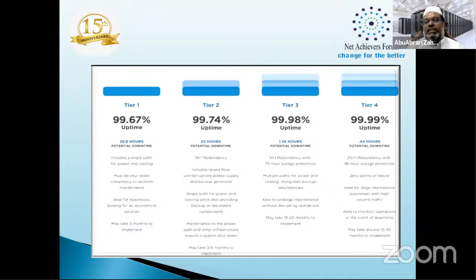Then coming to tier 4, it has 2 N+1, meaning you have one full path for power. For example, it has its own generator, its own UPS, its own main power source. So from the main power source, the UPS, the ATS, the batteries, the generator system, and the distribution system. You might have noticed every server has 2 different power sources, right? Each power source is a separate path all the way from the main, generator, UPS, and distribution unit, to your server. In case of power failure on one path, the other path will take over. So there will be no downtime whatsoever.